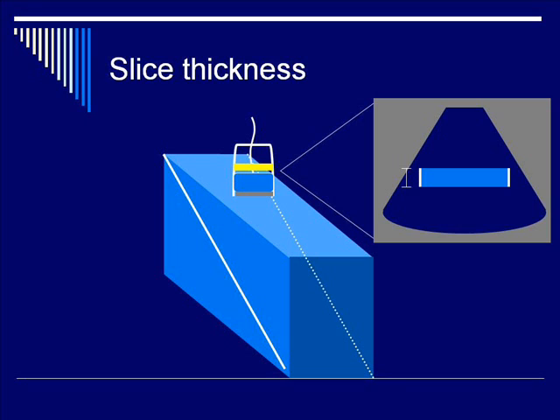Recall that slice thickness varies throughout the field, narrowing at the focus and expanding significantly past the focus. So you need to measure this at different depths, especially within the deep field.